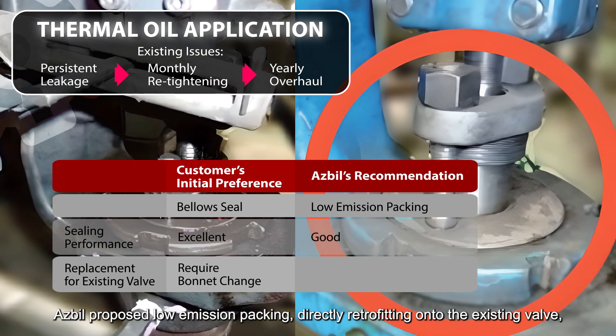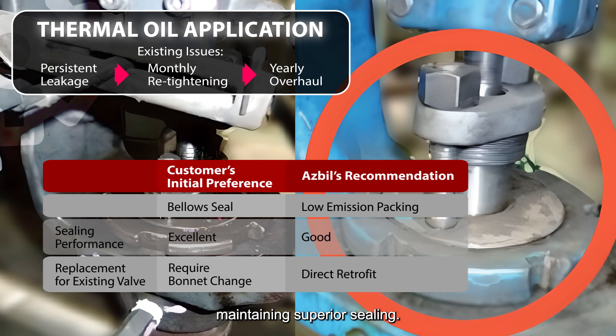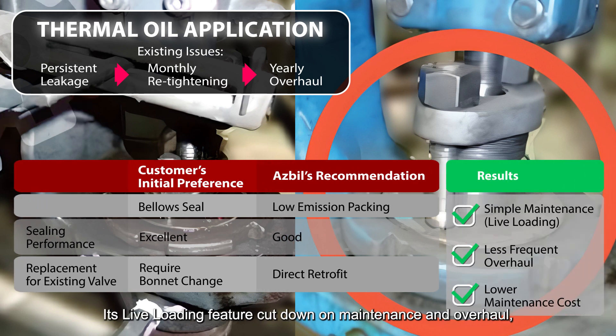Azbil proposed low emission packing directly retrofitting onto the existing valve, maintaining superior sealing. Its live loading feature cut down on maintenance and overhaul, reducing overall costs.